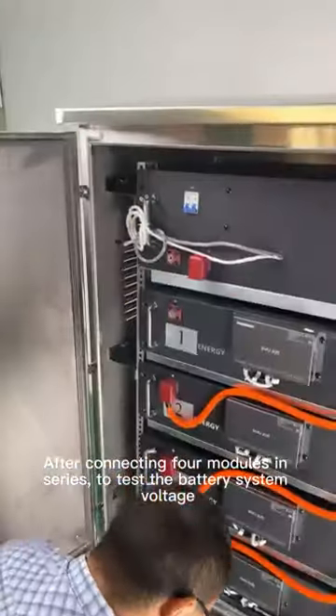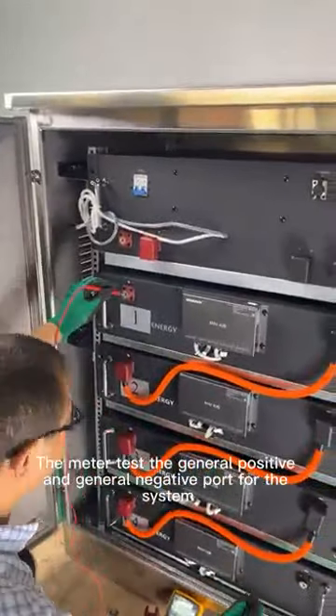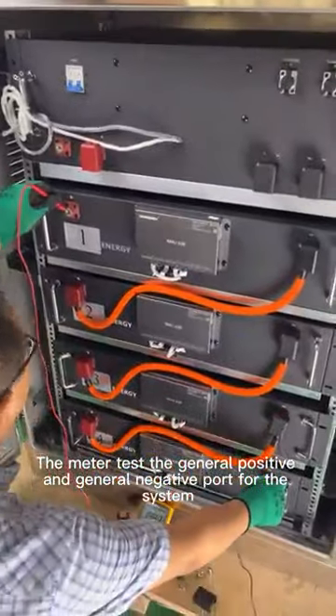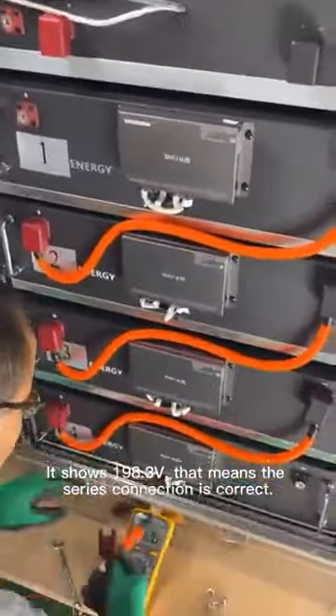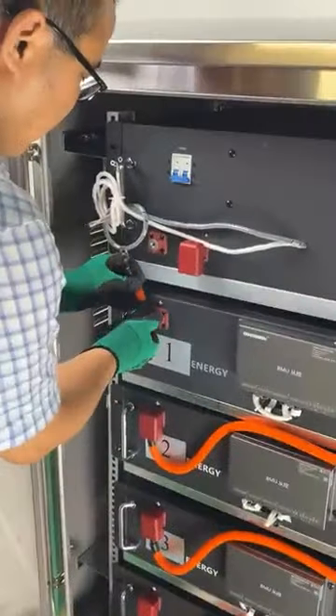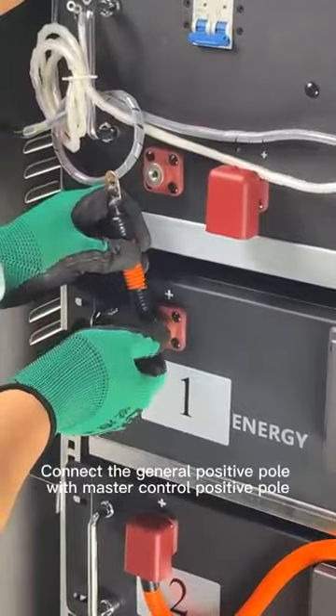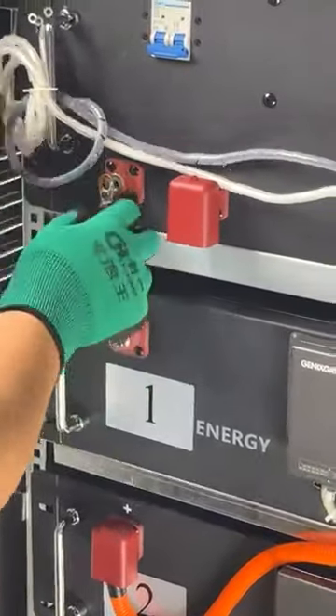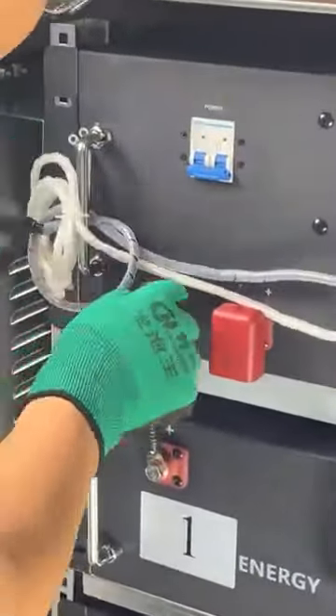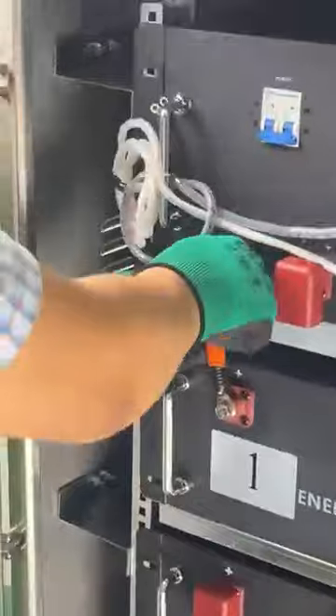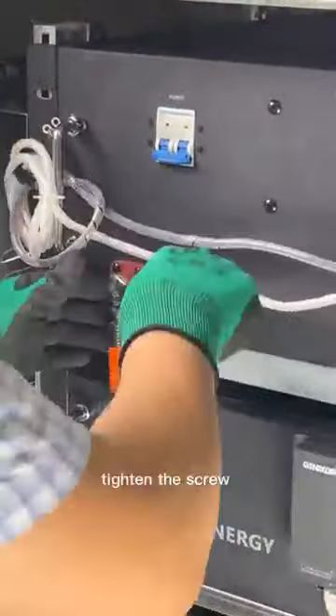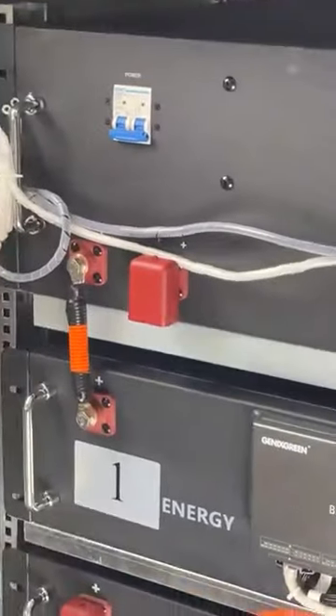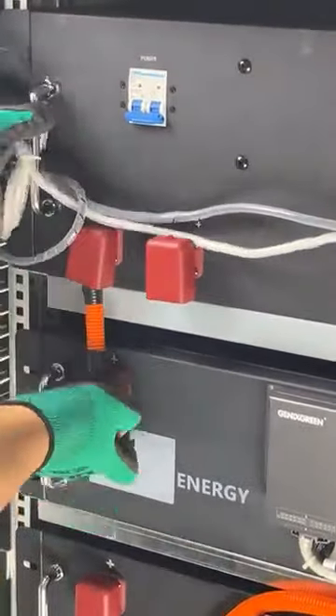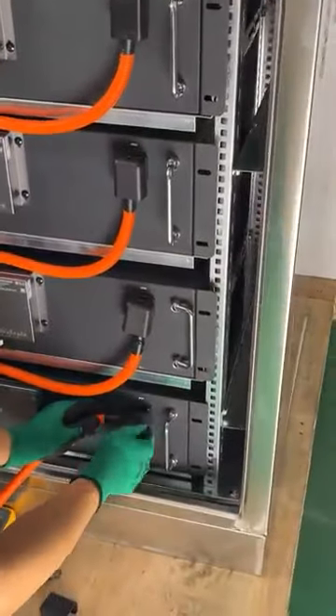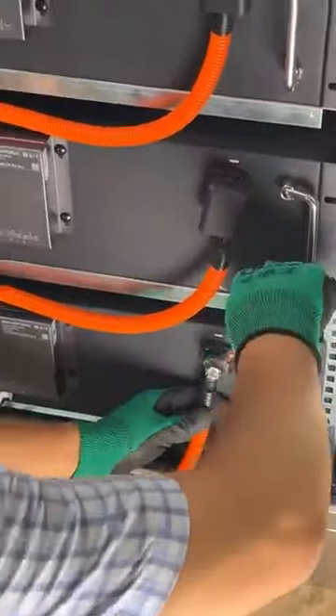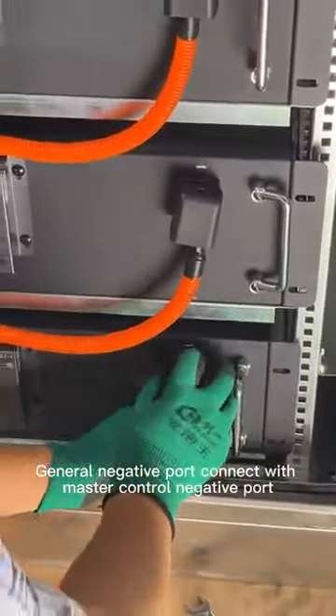After connecting 4 modules in series, test the battery system voltage. The meter tests the general positive and general negative port for the system. It shows 198.3 volt. That means the series connection is correct. Connect the general positive pole with master control positive pole. Tighten the screw. Buckle the protection sleeve. General negative port connects with master control negative port.